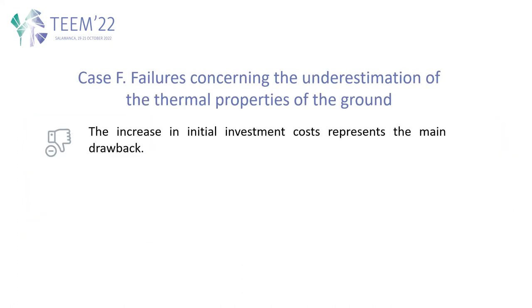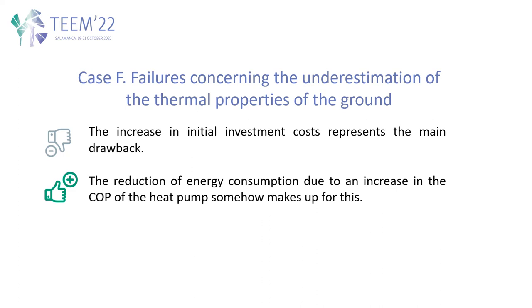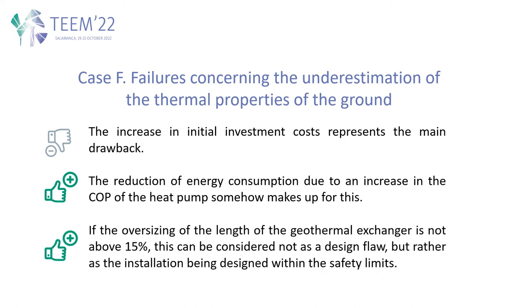And case F — that is, failures concerning the underestimation of the thermal properties of the ground — has one main drawback: it increases the initial investment. However, this also may cause the reduction of the energy consumption, due to an increase in the COP of the heat pump. And if we do not deviate more than 15%, under some circumstances, this may be considered a success.